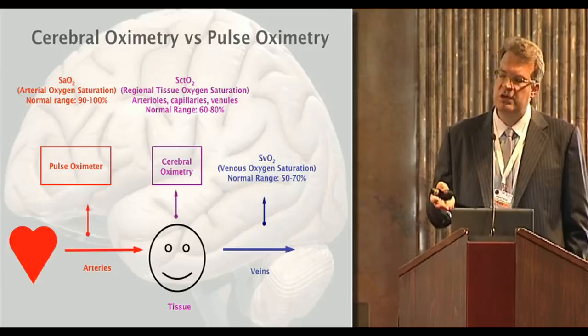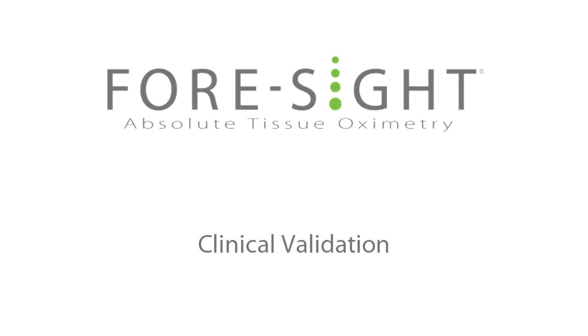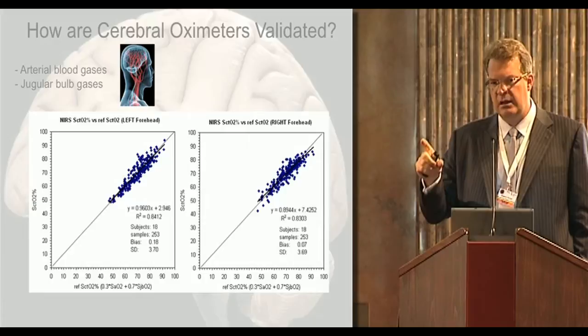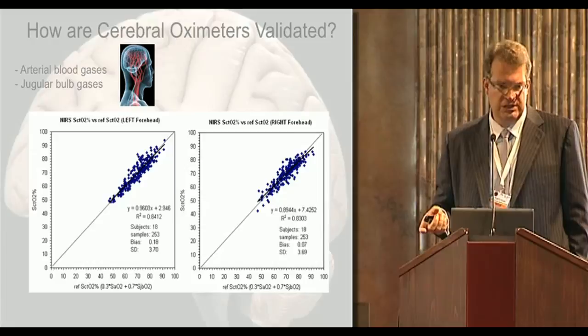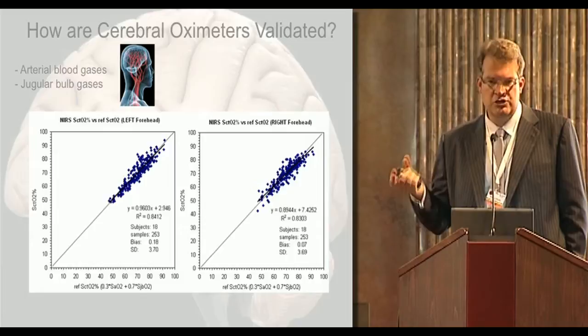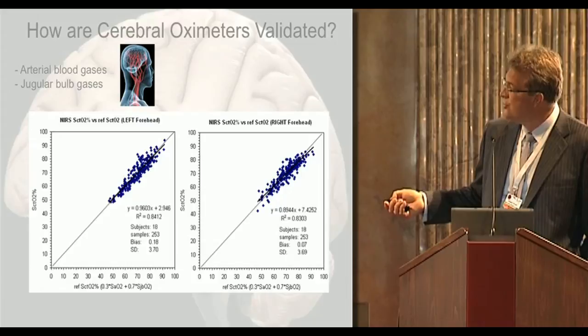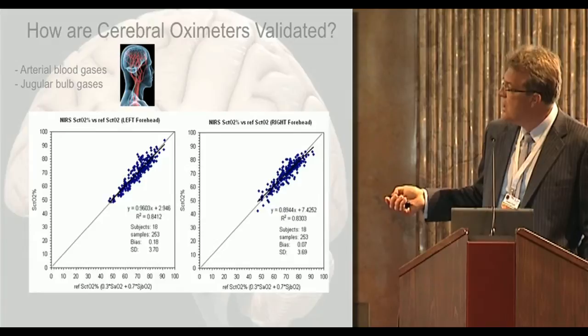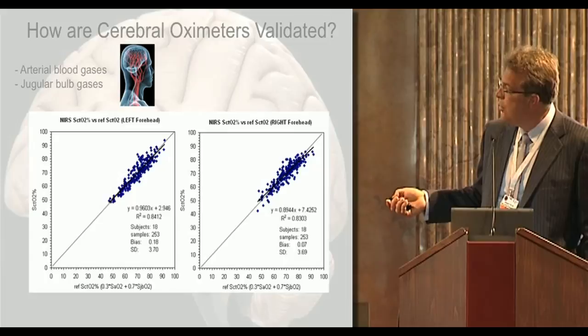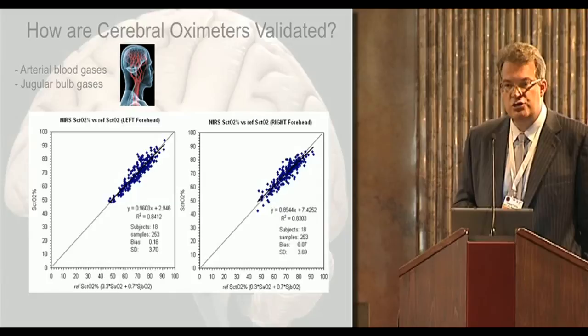What you're seeing on the screen has normal values somewhere between 60 and 80%. To know that the number on the screen truly reflects physiology, we have to measure it against the gold standard — invasive co-oximetry measuring arterial blood as well as jugular bulb blood. The cerebral tissue oxygen saturation is comprised of 30% arterial and 70% venous, so arterial saturation times 0.3, plus jugular bulb saturation times 0.7, should equal the number the machine displays.